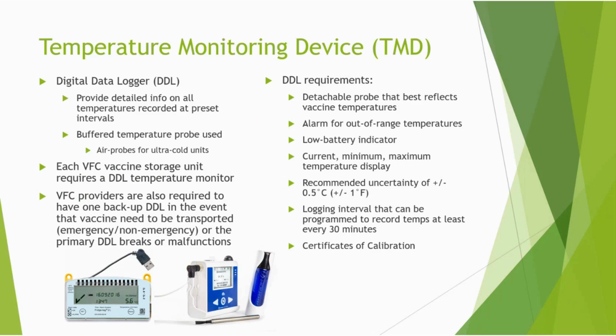Every vaccine storage unit must have a temperature monitoring device. An accurate temperature history that reflects actual vaccine temps is critical for protecting your vaccine. The CDC recommends the use of a specific type of TMD called digital data loggers, or DDL. DDLs provide the most accurate storage unit temperature information, including details on how long a unit has been operating outside the recommended temperature range. Unlike a simple min-max thermometer, which only shows the coldest and warmest temps reached in a unit, a DDL provides detailed info on all temperatures recorded at preset intervals.